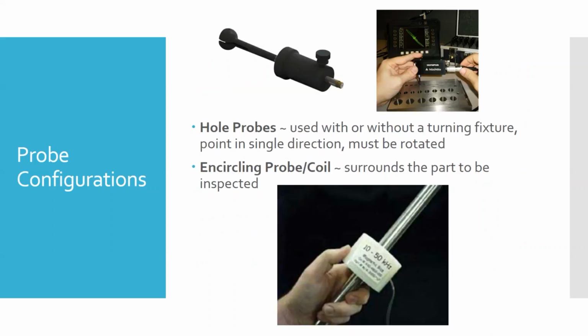Bolt holes are often inspected, so we have a bolt hole probe here. This is just the holder for it. This is to hold it against the surface. The actual probe is typically one little coil in this bulb. The bulb on the end is designed to push out against the inside of a bolt hole, and there's a coil on one side. We have these in the lab, and you can actually see where the coil sits in here. You put it down inside of a hole and then rotate it. The one shown in the picture here, ours, you put in the hole and rotate manually.